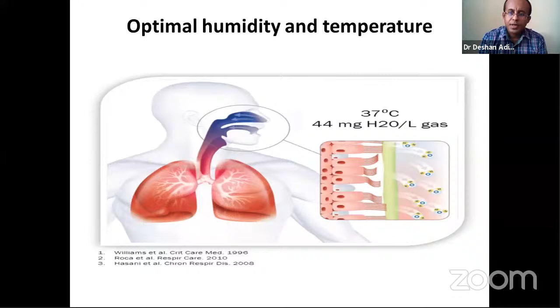Thirdly, the high velocity of gas flow. So if someone provides a face mask oxygen at 10 liters per minute with a high amount of oxygen, say 100%, under lab conditions, so up to 10 liters per minute, it is able to provide this amount of oxygen, 100%. But say you put this on a patient who has a greater work of breathing and greater oxygen demand. So in that case, assume that the patient is developing and needing a peak flow of 30 liters per minute, but we are providing only 10 liters per minute with this amount of oxygen. So the rest will be mixed with the air. So the patient will get only a mixture of this.